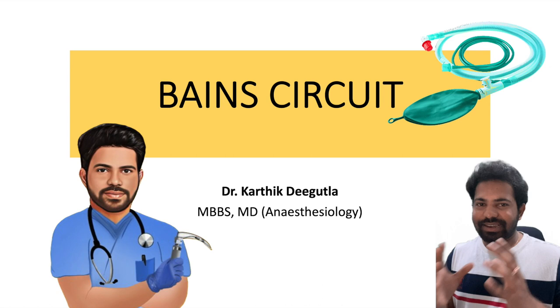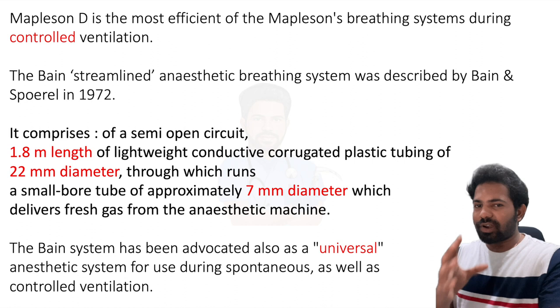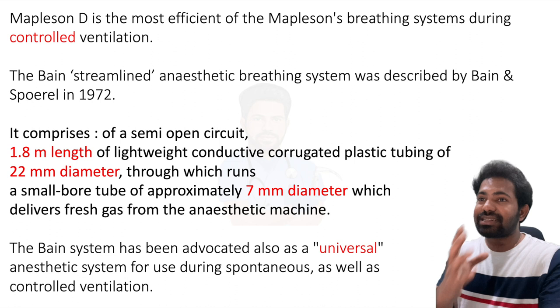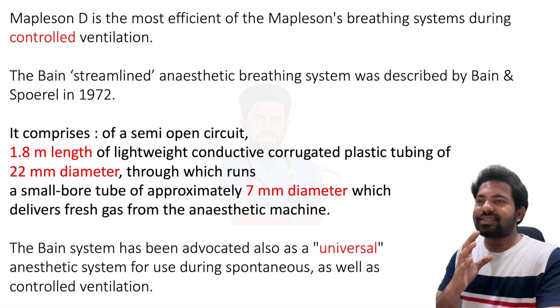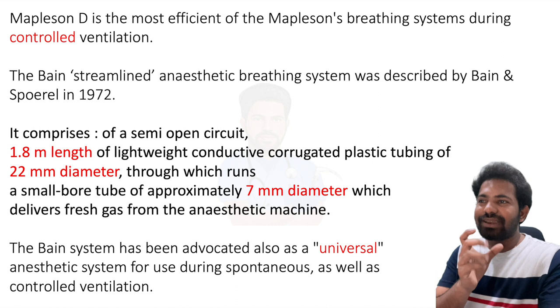Bain circuit is a modification of Mapleson D. Mapleson D is the most efficient of the Mapleson's breathing systems during controlled ventilation. It was after 1972 that the Bain streamlined anesthetic breathing system was described by two people: Bain and Spoerel.